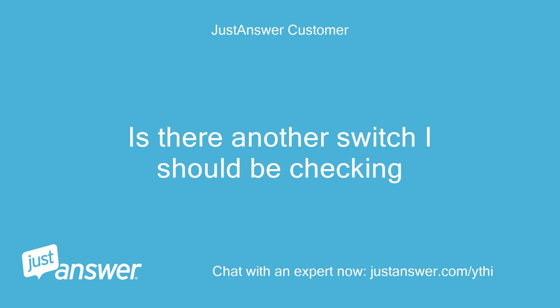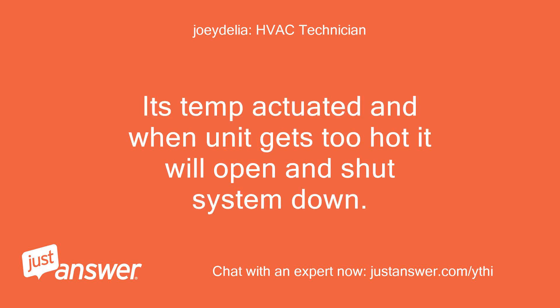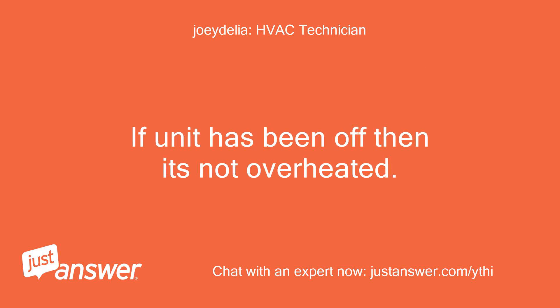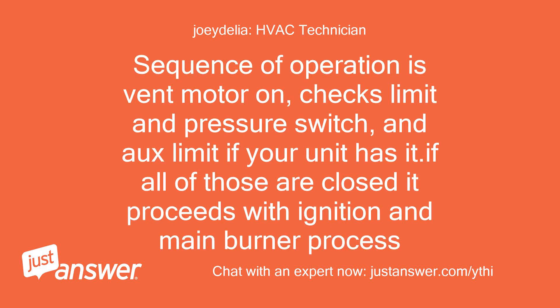Is there another switch I should be checking? A limit switch will have two wires coming from it. It's temperature-actuated, and when the unit gets too hot it will open and shut the system down. If you say the unit starts up, runs, and gets to temp, then when it tries to come back on it fails to light and throws this code — if the unit has been off then it's not overheated. The pressure switch may go through that circuit also and if it does not close on startup it may trigger that code. Sequence of operation: vent motor on, checks limit and pressure switch and aux limit if your unit has one. If all of those are closed it proceeds with ignition and main burner process.